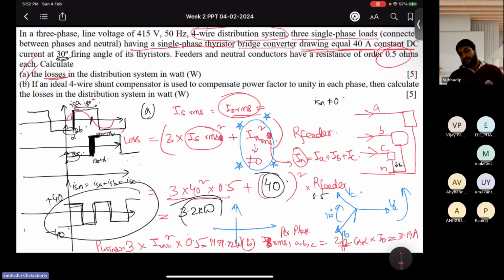Just remember one thing, without compensation, when you are not using any compensators, your neutral current for nonlinear loads may not be zero in all cases. Just draw the waveform and see. So for this kind of waveform, you don't need to again do, because you have already drawn, and if you have not, then you can draw the waveform displaced by 120 degree, sum them up, you will see that you have got oscillating currents, square shaped currents. And after compensation, since neutral current is compensated, then you can just assume that neutral current RMS value is zero, and the losses will not happen for neutral current. So the losses will also reduce due to the compensation, unity power factor after the compensation.